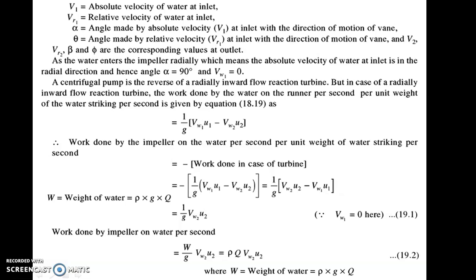The impeller power is given by the formula Rho Q into Vw2 U2. For a pump, the input power is shaft power which is supplied by the electric motor, so electrical energy is the input power or shaft power. Then after shaft power there is impeller power, which is the work done by the impeller on the water, given by Rho Q into Vw2 U2. In terms of head, it will be given by Vw2 U2 upon G.